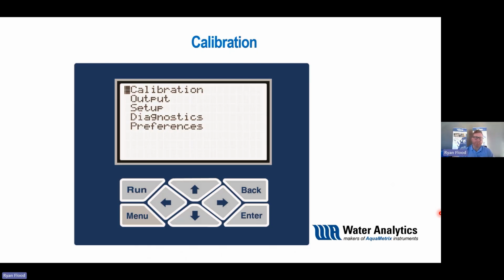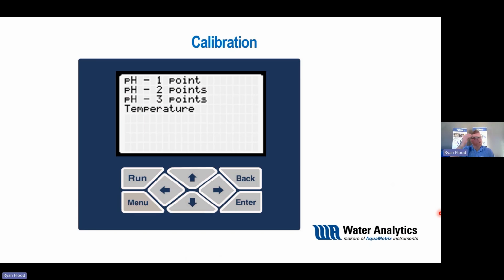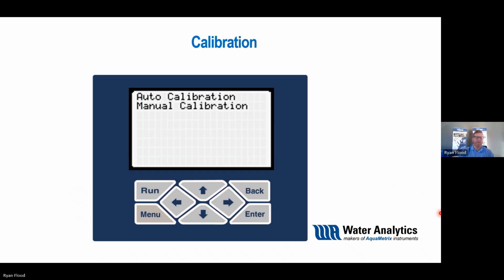Pretty straightforward. You go to the screen, you start off with your calibration, and you're going to choose the number of points. We typically always recommend a 2-point calibration. You can go with more points if you want as well, but 2 really is the sweet spot. It's going to give you some of your best readings. And then from there, you get to choose auto calibration or manual calibration.